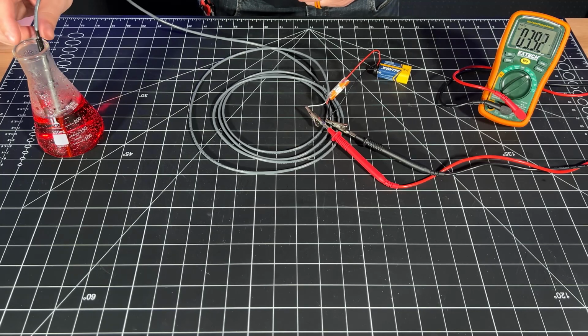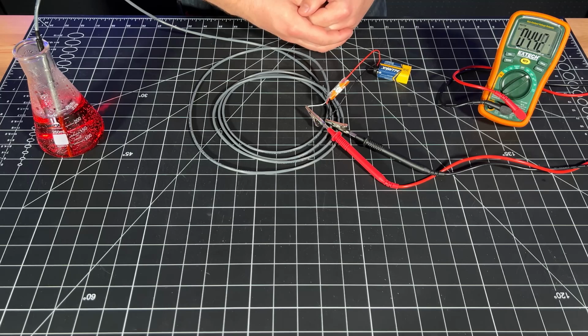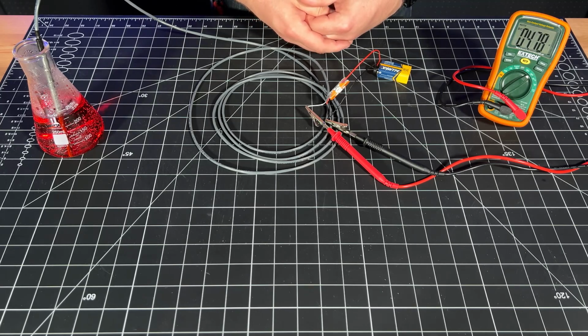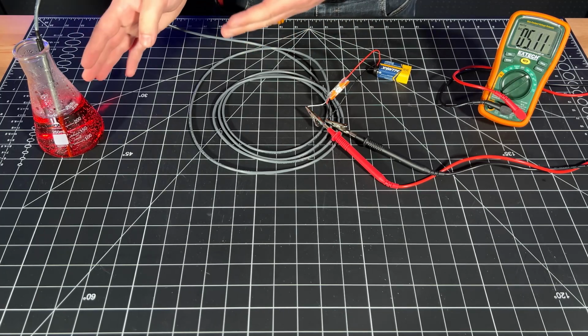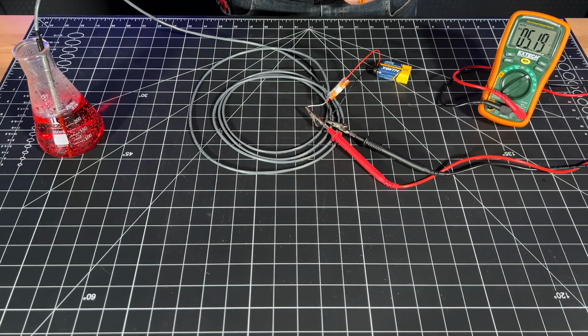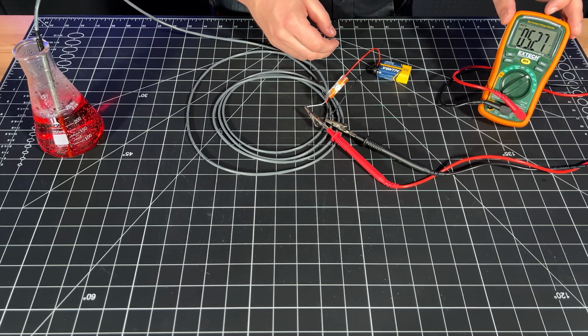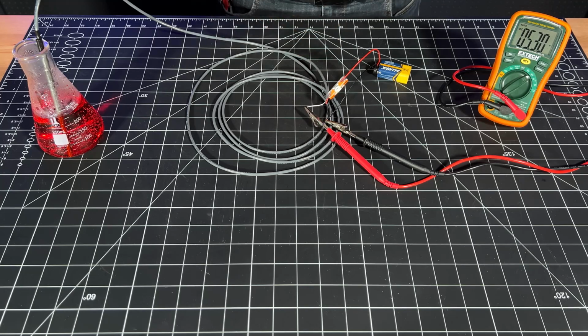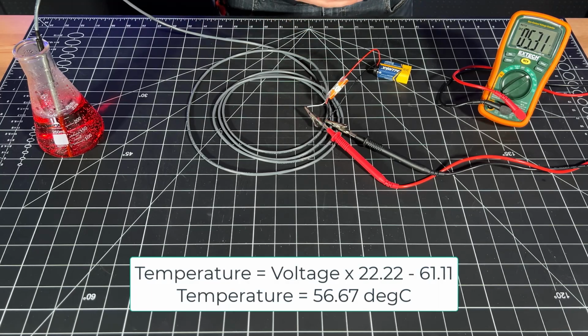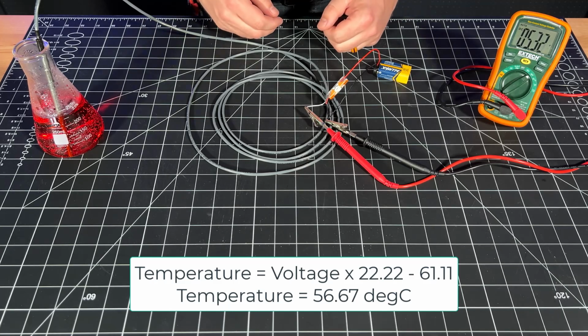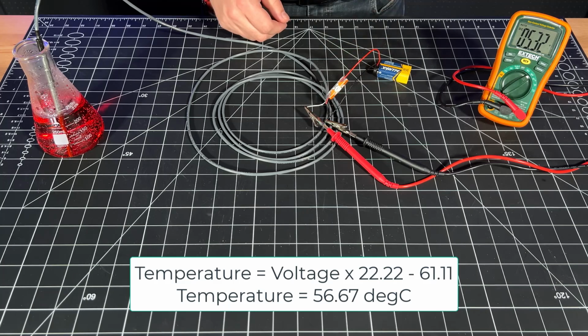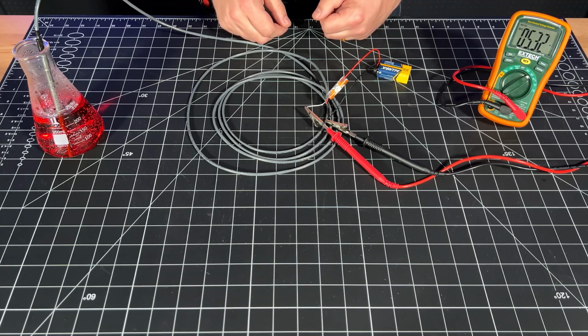But let's go ahead and put the probe into some hot water here. We can see our output voltage is climbing quickly as the probe begins to heat up and equilibrate. Remember, there's a decent amount of thermal mass in this probe, unlike a very small thermocouple. And we can see that we're slowing down here at about 5.3 volts or so, 5.29. So we can plug that again to our math and see what temperature the water is. This is a really easy formula, and you can easily program it into most data acquisition softwares, or even just read the meter and use a spreadsheet to find the instantaneous temperature. So as you can see, this is a really simple probe to use.